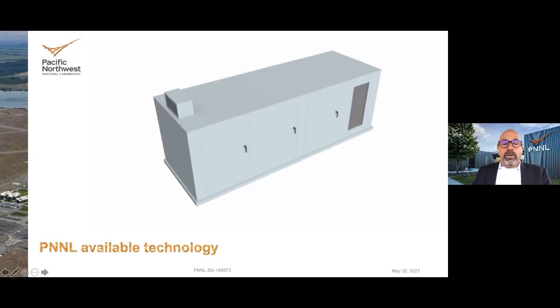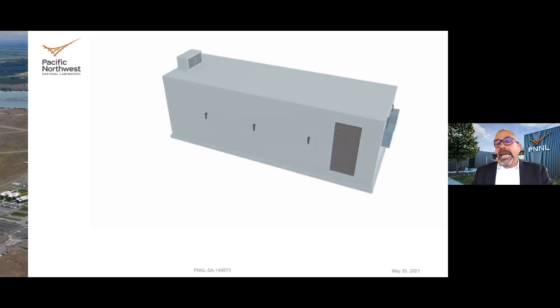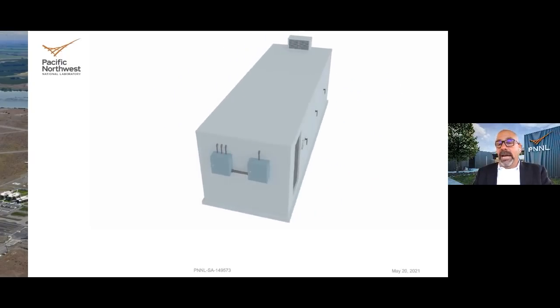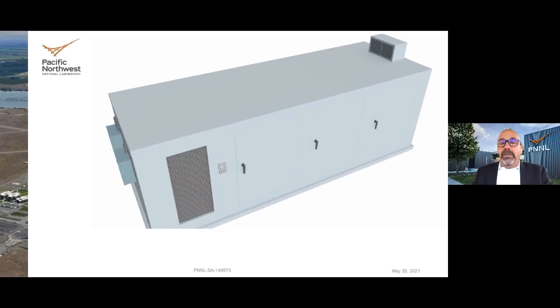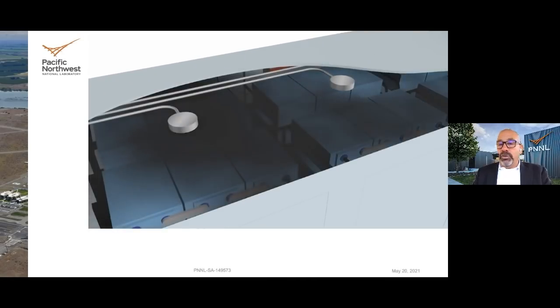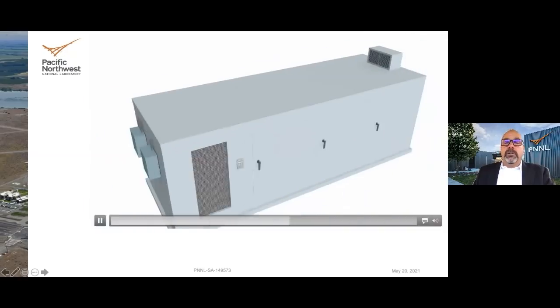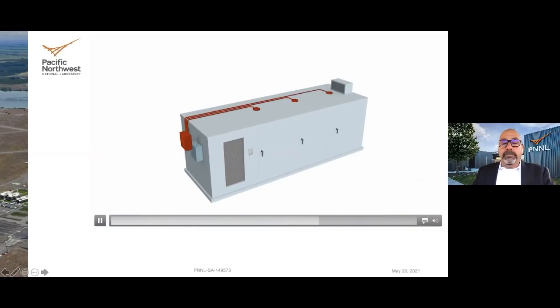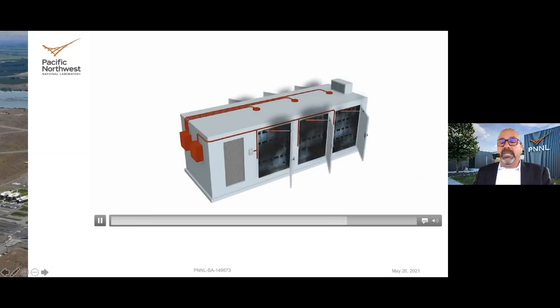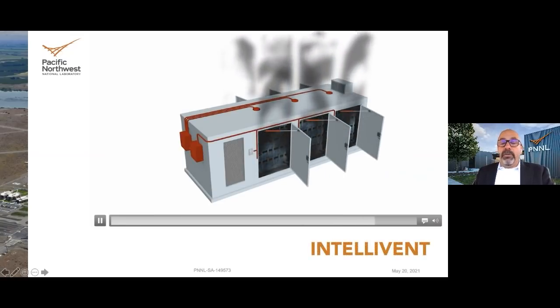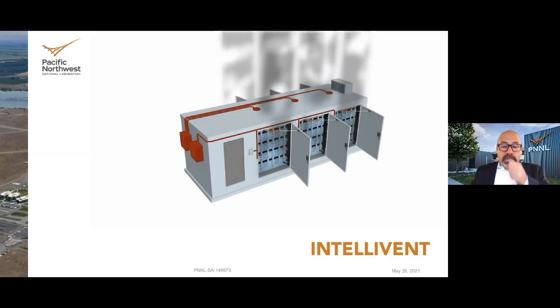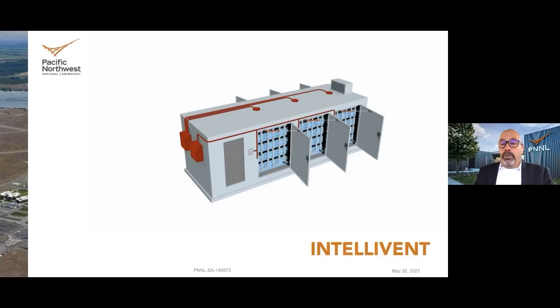So we came up with a technology that we're calling IntelliVent. This is an example of a cabinet, again accessed from the outside. In the event of a catastrophic failure, some type of sensor inside — it could be smoke, heat, or gas — would tie into a fire alarm panel. That fire alarm panel ties into the IntelliVent system, which opens all of the doors at a very early stage. Obviously this is a very simple approach, but we feel it's essential for cabinet-based ESS. Opening the doors allows a dilution solution for the gases.